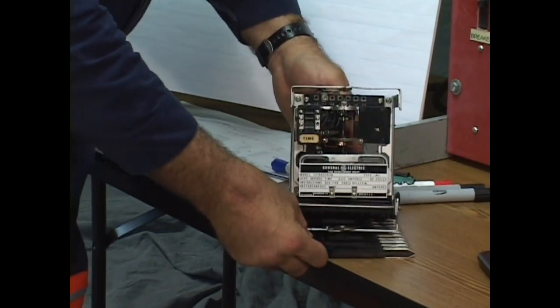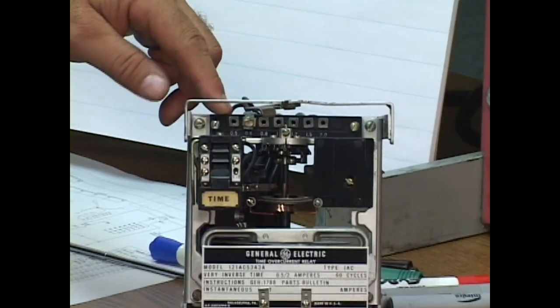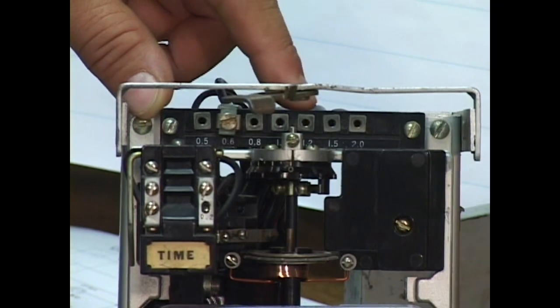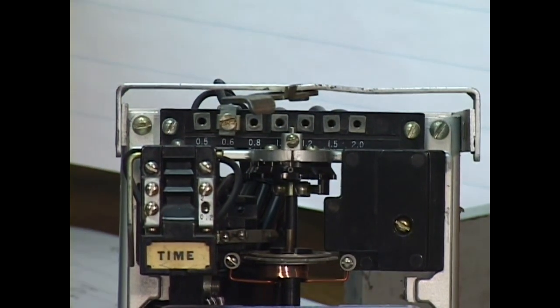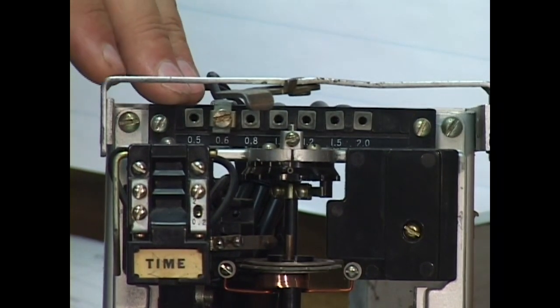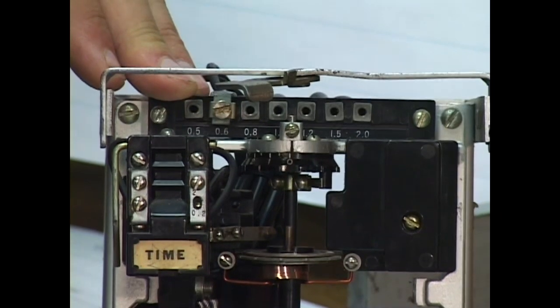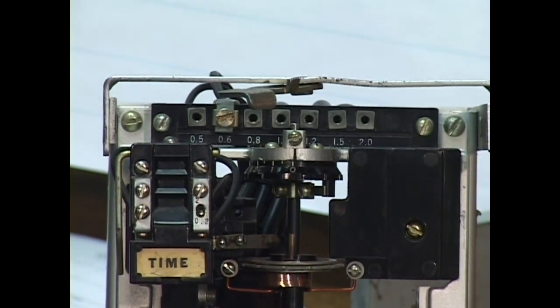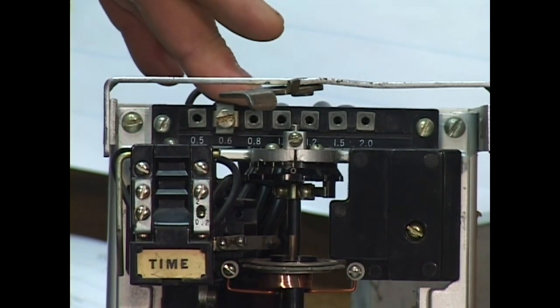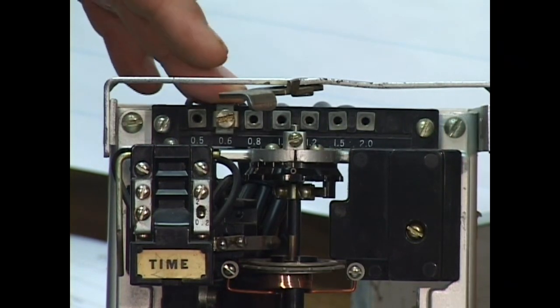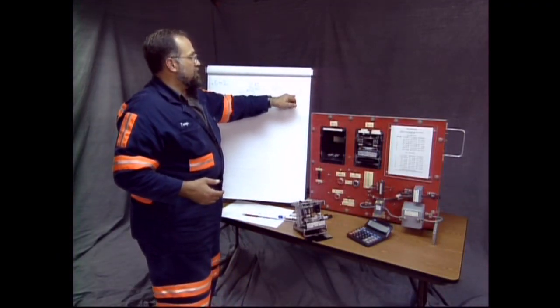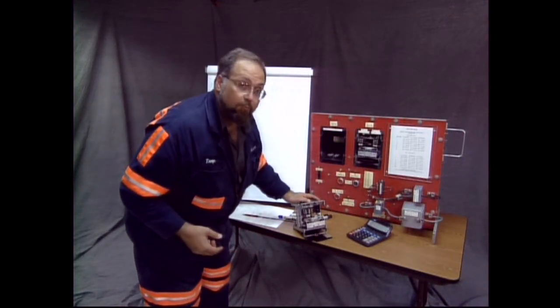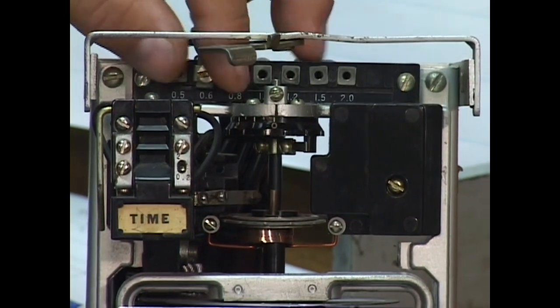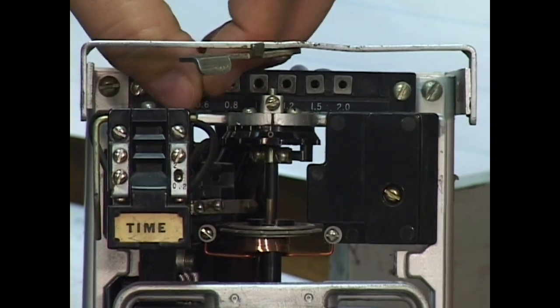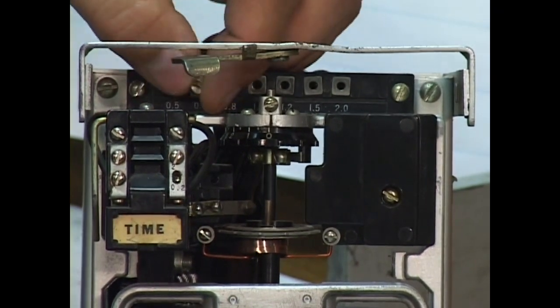If you take the relay out, just like with the phase, you have a row of taps: 0.5, 0.6, 0.8, 1.0, 1.2, 1.5, and 2. Now these relays are very diverse. I think the state panel that we used last in testing at the Oak Hill office had a 0.5 to 4, so these values will be changed. Whatever tap you're going to set to, make sure you actually have that physical tap. Now I said that we wanted to set at a tap of maximum 1.25. We don't have a tap 1.25. The closest we can come to that without exceeding it is a tap of 1.2. So we're going to loosen this set screw and slide this over to 1.2.